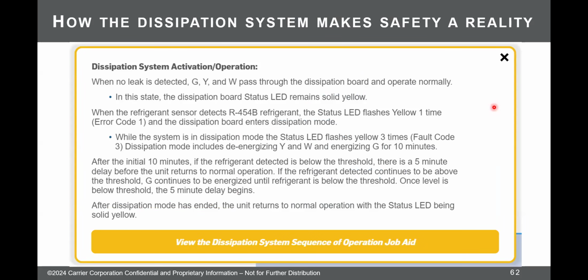If there's a leak detected, so if we get to 20% of the lower flammability limit for any given refrigerant, in this case 454B, it detects a leak. It is required to shut off the condensing unit. That makes sense. There's no reason to keep trying to run the compressor with refrigerant pouring out of this thing, right? So shut off the condensing unit, shut off any sources of heat, meaning gas furnace or electric heater.